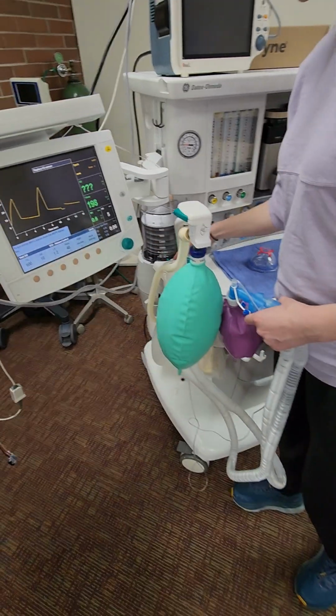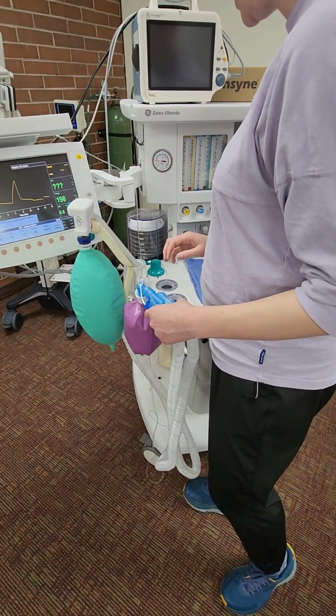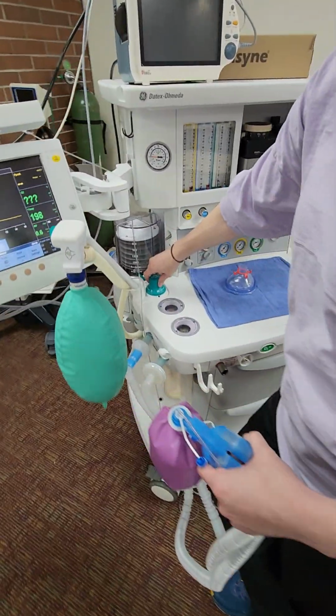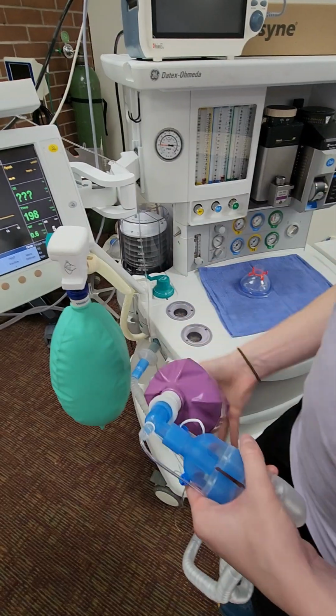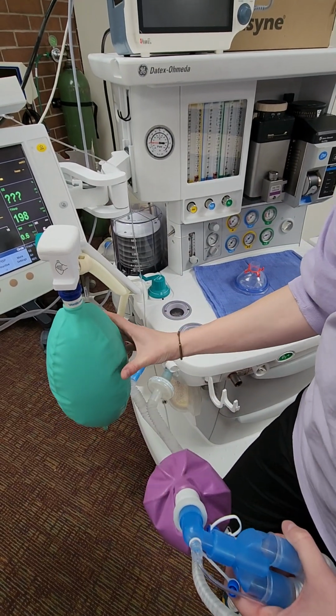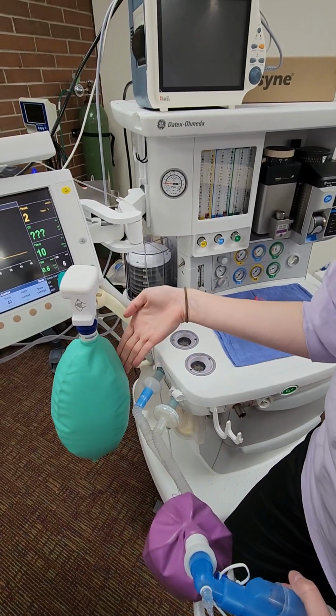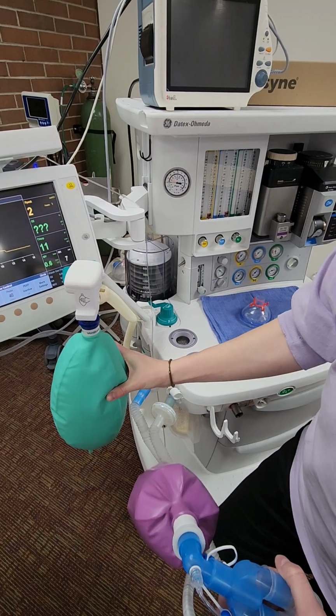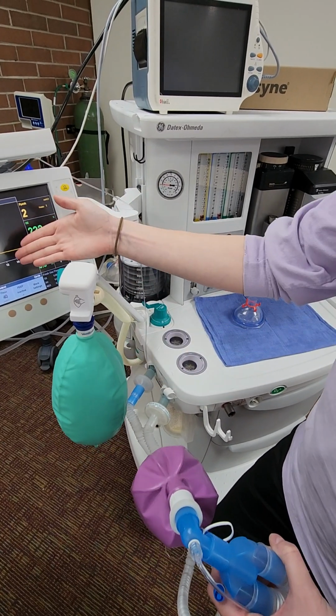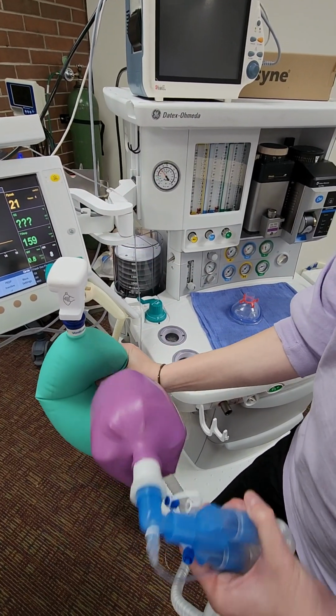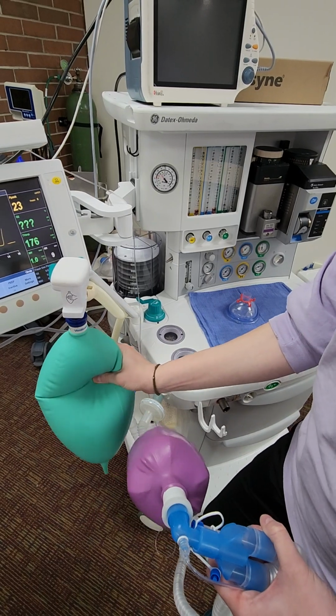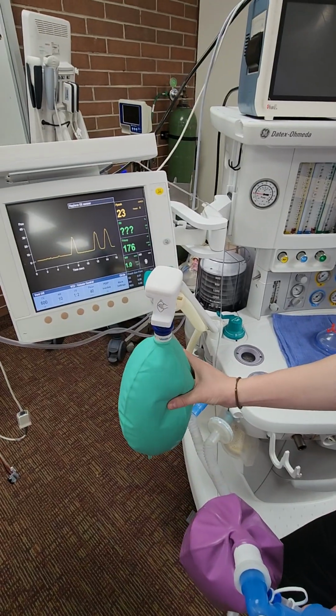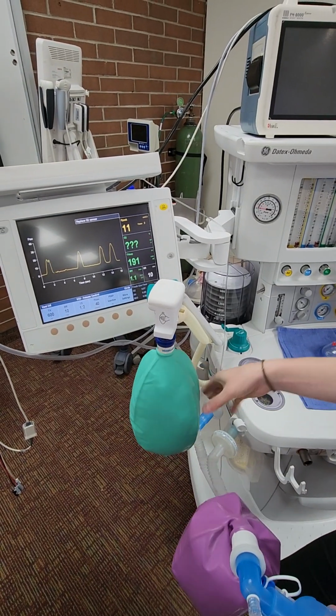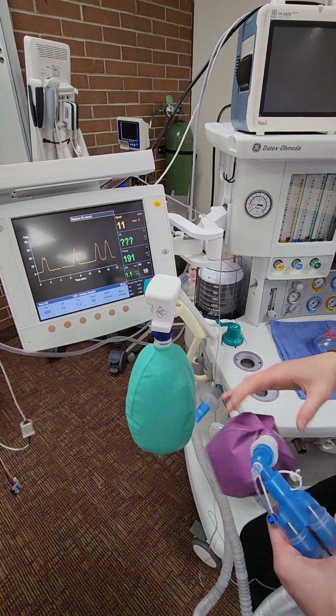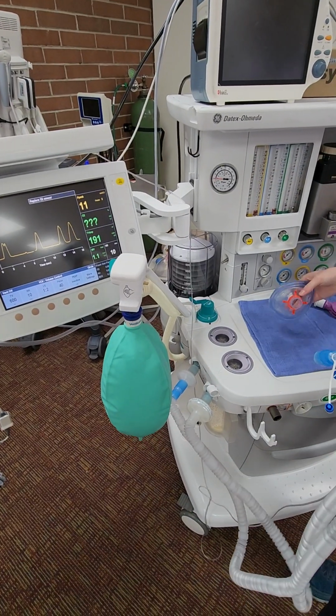You can flip this back to manually bagging your patient, and you'll close your APL valve to 20, and then check your lung, check this green thing, squeeze it, and then it'll reflect on the monitor, and it should reflect in your false lung that you are delivering breaths to your patient. And once you think you have successful manual ventilation, you can disconnect your fake lung and then proceed to start up for surgery.